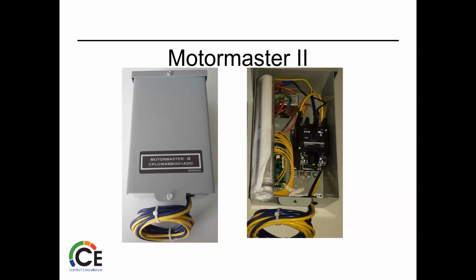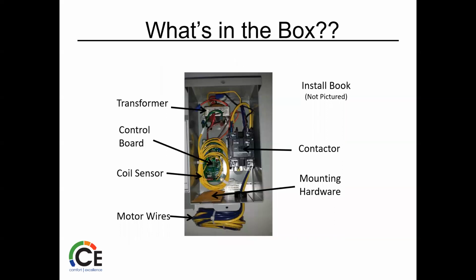So Motormaster II, again, that's another option depending on which unit we have. It does come in a control box at this point, instead of just some controls in a box, right? So you've got a nice control board there, coil sensor, the wires to your motor, contactor, and some mounting hardware to screw it on there. Pay attention to which door you screw it on. I've seen plenty of pictures where it was put on a filter door, and now you can't get the filter off. So again, silly stuff, but watch where you're mounting that.